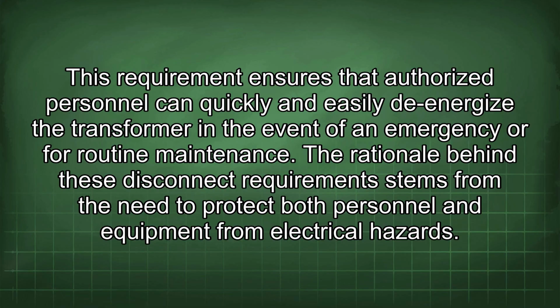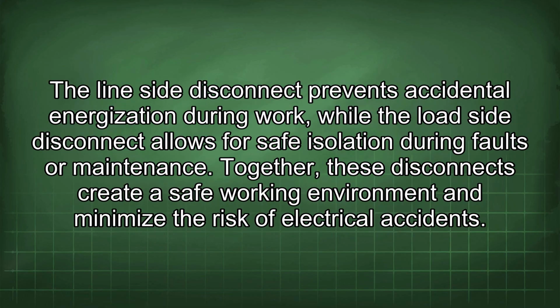for routine maintenance. The rationale behind these disconnect requirements stems from the need to protect both personnel and equipment from electrical hazards. The line side disconnect prevents accidental energization during work, while the load side disconnect allows for safe isolation during faults or maintenance. Together, these disconnects create a safe working environment and minimize the risk of electrical accidents.